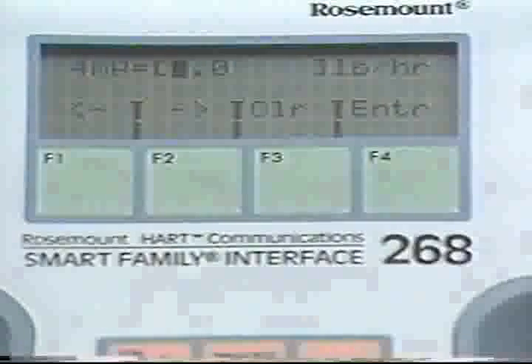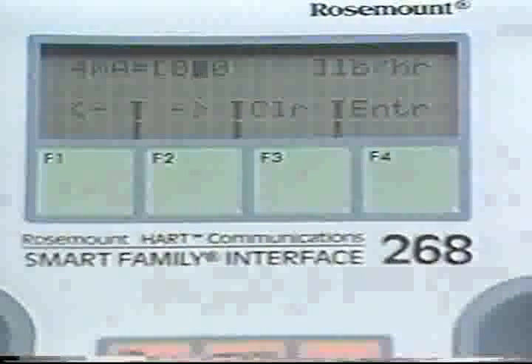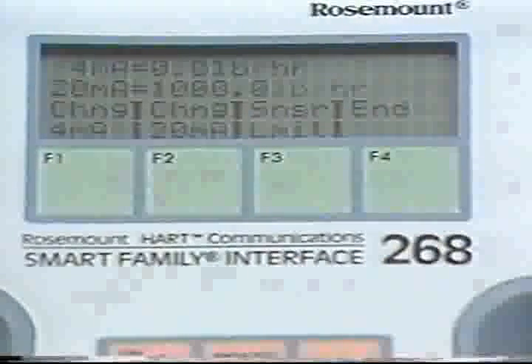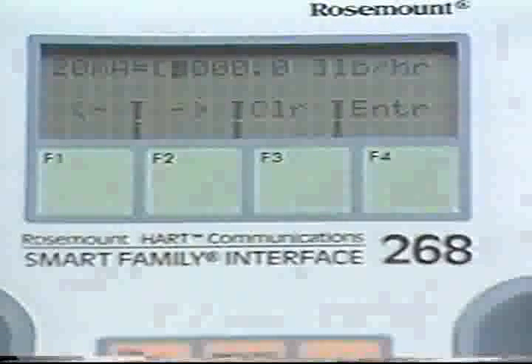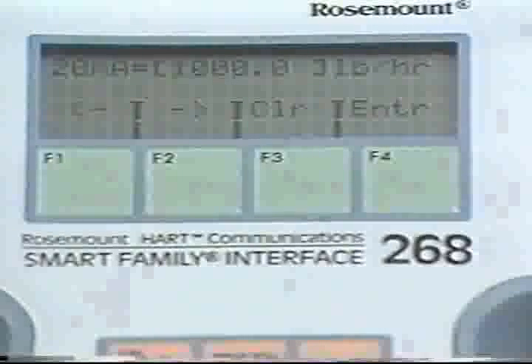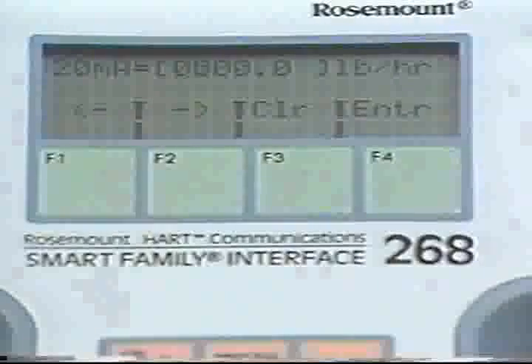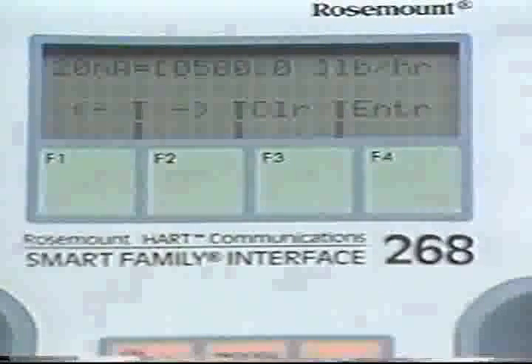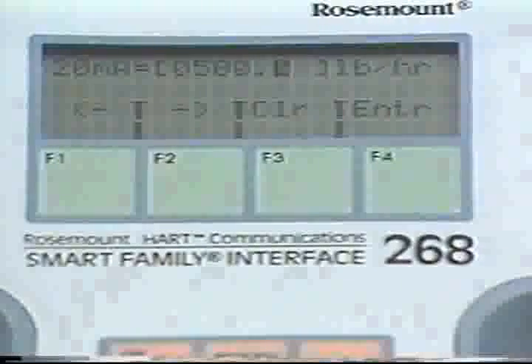Let's look at an example. In this case, the new range for this instrument is 0 to 500 pounds per hour. The low range value displayed here is correct, so Enter is pressed to proceed. However, now the upper range value that's displayed is inappropriate. It should be 500 pounds per hour. To change this value, you'd press the function key for change and then enter the new value using the appropriate alphanumeric keys. Now the specific information for the instrument in the loop is displayed.